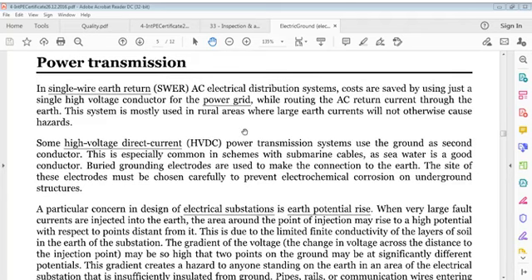In single wire earth return, SWER, an AC electrical distribution system, costs are saved by using just a single high voltage conductor for the power grid while routing AC return current through earth. This system is mostly used in rural areas where large earth currents will not otherwise cause hazards.